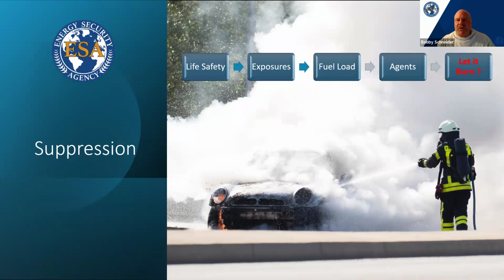Let me dig into your foams and agents, whether they're an emulsifier or an encapsulator. Think of it this way: a lot of times certain agents are actually conductive themselves, so they actually propagate the situation. But even the ones that aren't, they disrupt the fire tetrahedron, so they'll knock out flame, but they don't stop thermal runaway. And remember, if I'm not burning, I'm producing a mass amount of off-gassing, creating an explosive environment. So now I've got the buildup of all that off-gassing, and as that encapsulating or emulsification agent dissipates and wears off, everything's back to the LEL. And instead of reignition, a lot of times I get an explosive situation, then back to reignition. So the foams and agents can actually create worse conditions through their mechanism of action.